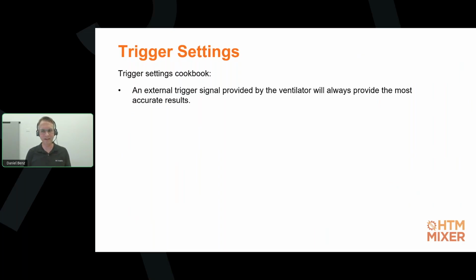So some ventilators have an output that says trigger, and it creates a digital signal whenever the breath phase starts and when it changes to exhalation. Because the ventilator controls the ventilation and can tell the analyzers through the digital signal when the transition from one breath phase to the other happens, this is the most accurate we can go, all right?